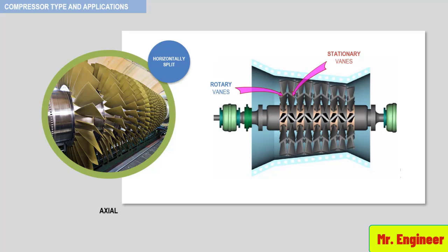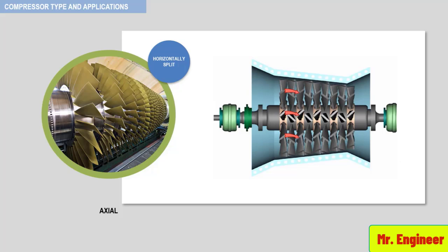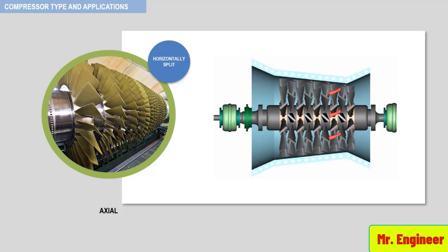The rotation of the rotating vanes with respect to the stationary vanes determines the flow path of the gas. The gas alternately changes direction as it passes through the rotary and stationary vanes, which are inclined at different orientations with respect to each other. The rotating vanes impart velocity and pressure to the gas. The working principle of this axial compressor is now seen at a different angle.